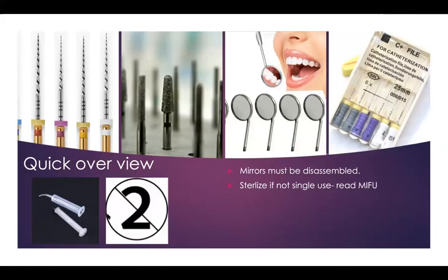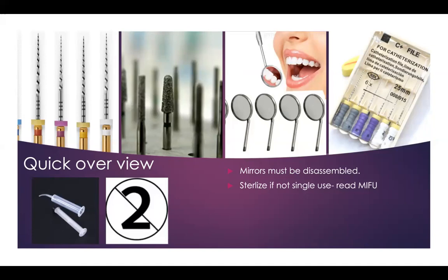We have a lot of instruments and materials. One thing I have to stress is that mirrors have to be disassembled — you cannot have the handle and the mirror together and sterilize them as one. You have to disassemble and sterilize separately, though you can have them in the same pouch. For endofiles, some manufacturers make them single-use and you will find the single-use symbol on them. Some are not single-use, so you can sterilize them. You must follow the manufacturer instructions.